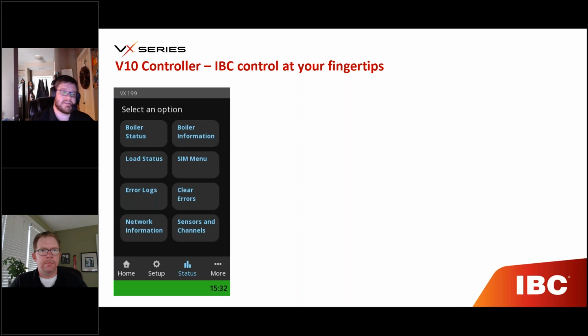Our sim menu is where you can check into all your safety sensors and stuff like that. It has an operational ladder, so you can see what the boiler's doing at the time—is it in the burner cycle, has it had a call for heat, what's the flame signal. This is also where you can test your low water cutoff and water high limit for code reasons, if you have to do that for government reasons. I've got a couple commercial facilities where they have to do that. That's where you would run those types of tests.